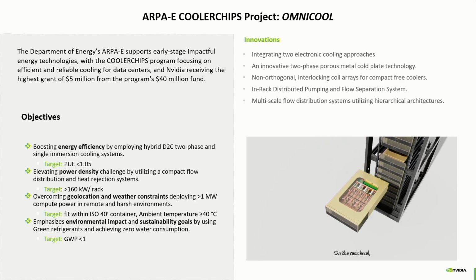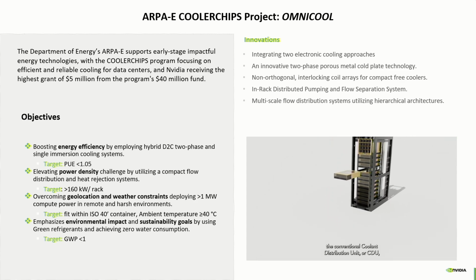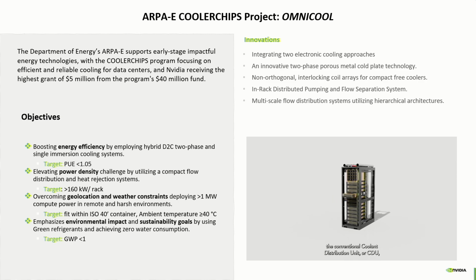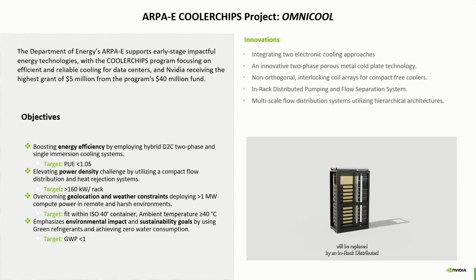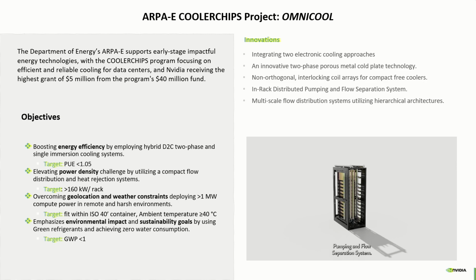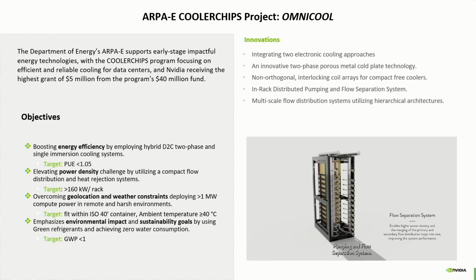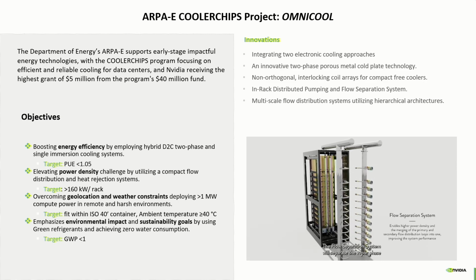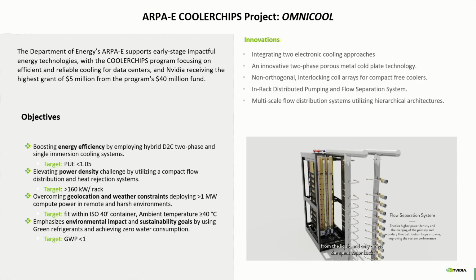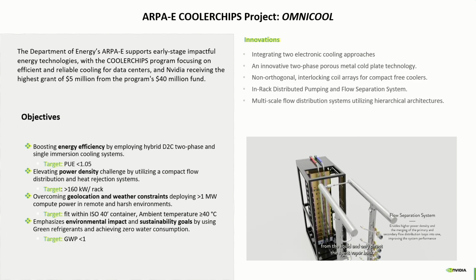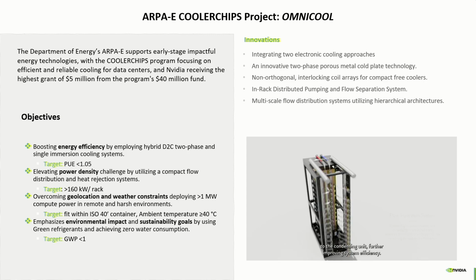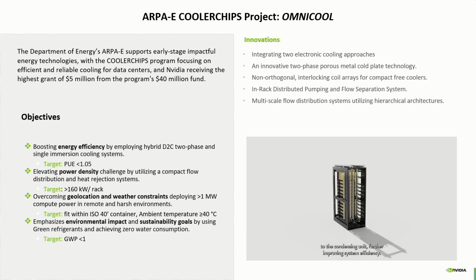tray. On the rack level, the conventional coolant distribution unit, or CDU, will be replaced by an in-rack distributed pumping and flow separation system. The flow separation system will separate the vapor phase from the liquid and only direct the spent vapor back to the condensing unit, further improving system efficiency. Similarly, the immersion manifolds will be connected directly to the heat rejection unit.